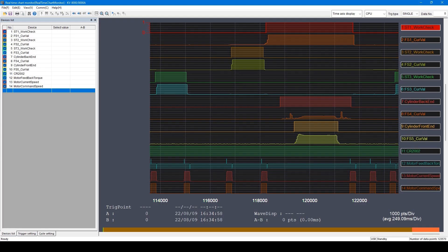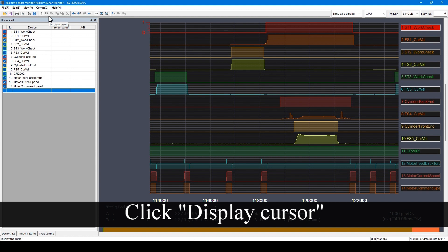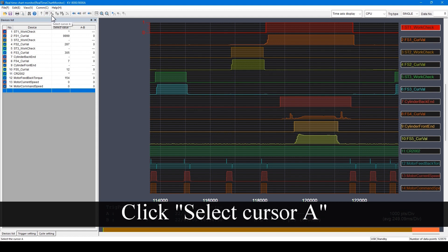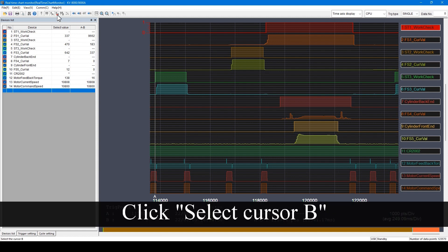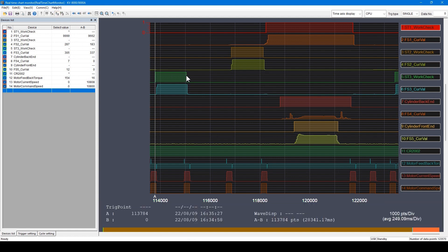I will introduce how to measure the time between two points. To acquire the on time of this variable in the real-time chart monitor, click this icon so cursor A is selected. While this variable is on, locate the cursor A. While cursor B is selected and when the variable turns off, locate the cursor B. Then the time between cursor A and cursor B is displayed here.